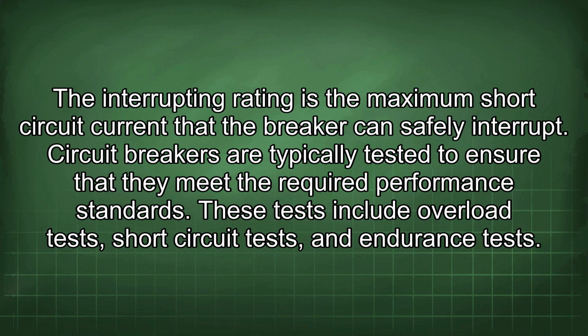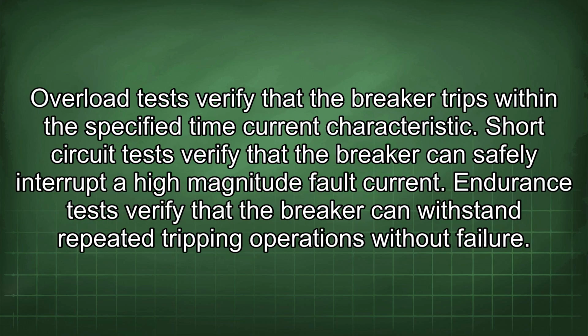Circuit breakers are typically tested to ensure that they meet the required performance standards. These tests include overload tests, short circuit tests, and endurance tests. Overload tests verify that the breaker trips within the specified time current characteristic. Short circuit tests verify that the breaker can safely interrupt a high magnitude fault current. Endurance tests verify that the breaker can withstand repeated tripping operations without failure.